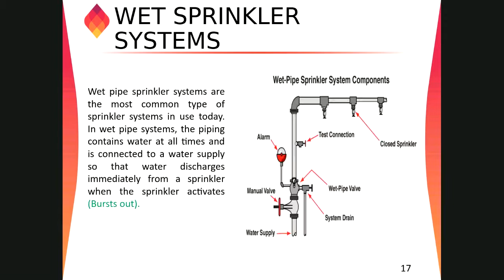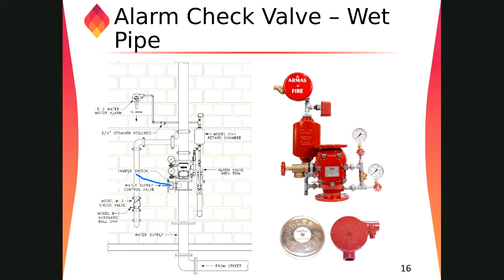Now, what is the tamper switch? If you close a valve, it will give a signal. It is connected to the fire alarm panel. If you try to rotate the valve, after 2 or 3 turns the system will signal that someone is closing the valve. Most of the time a fire protection system fails only when there is a fire and the main control valve is closed. If the valve is closed, water is not getting to the fire protection system, and then the fire grows and the system will not work. So this should be supervised by the tamper switch, so that no one can play with it.